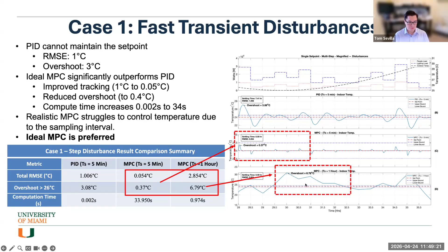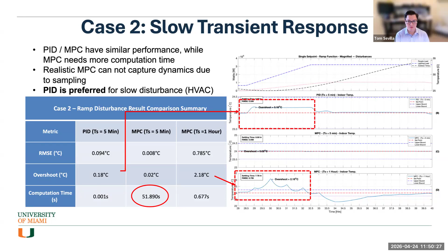Now, on case two, we have the slow transient response. As you remember, we have this ramp function where we're slowly turning on all our inputs for the people load as well as the lighting load. In this case, both the PID and the MPC are able to control the disturbances pretty well. You see that the PID only overshoots by around 0.2 degrees C, while the ideal MPC barely overshoots. We're looking at 0.02. But again, the computation time is much, much larger. We're looking at 52 seconds compared to 0.001 of a second for PID. So in this case, if you're comparing those two control systems, the PID is preferred. You still have pretty good, or I would say just as good, set point control, but your computation time is much lower. Your hardware complexity is also much lower at that point.